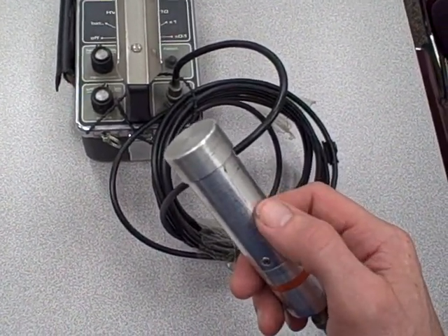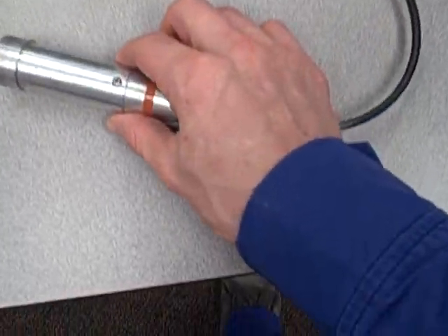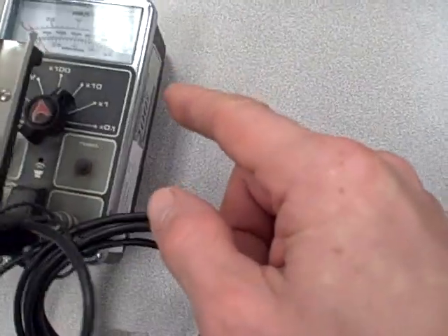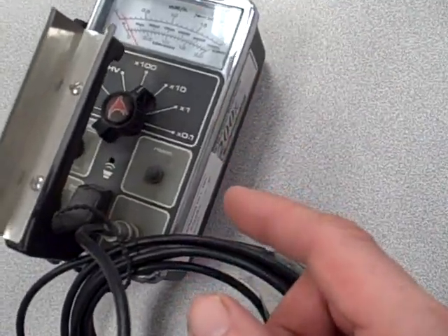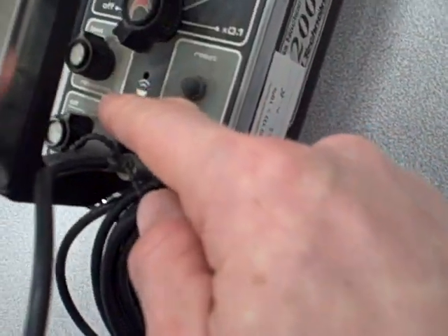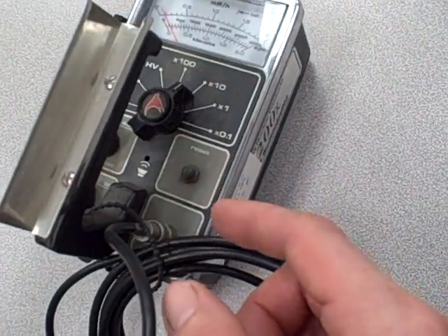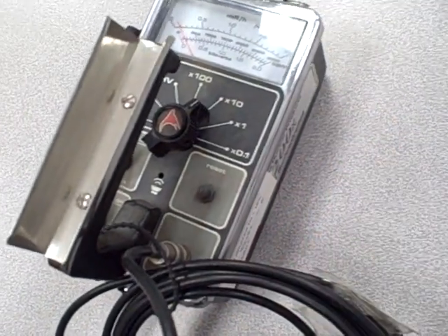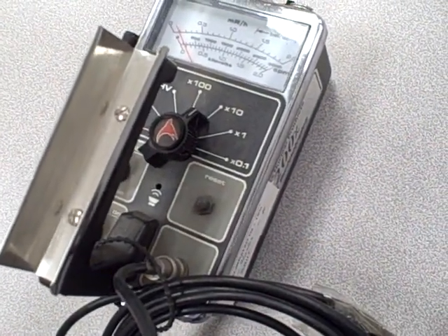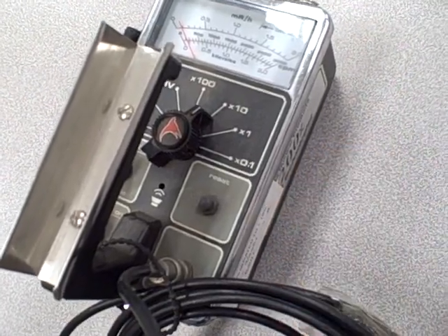When ionizing radiation passes through the wall of this chamber, it ionizes the molecules of gas within the chamber. That causes a brief spike of electrical current, which is conducted through this cable right here into here, and those spikes are counted. What you hear at that speaker, that clicking noise, is actually not one click per spike, but rather one click for lots of spikes and currents coming in.